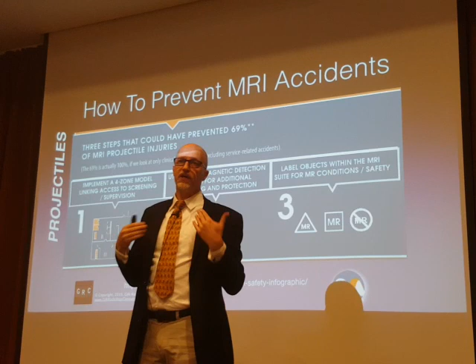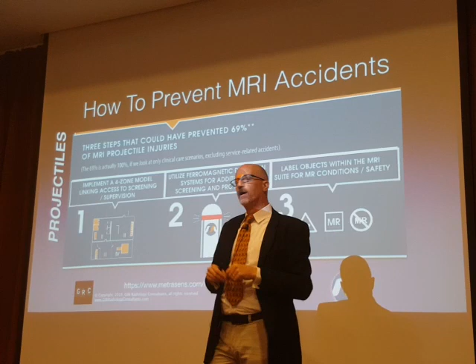For those of you who may not be familiar with the ACR 4-zone, essentially it means the closer we get to the magnet, to the MRI, or to the room that has the MRI in it, the more we're going to make sure that individual is screened or trained, or we are going to lock them out. Unless they're screened, trained, and supervised. So it's a bullseye. As you move closer towards that center ring, towards zone 4, where the MRI is, you have to go through increasing levels of screening, security, and supervision. And that's the basic premise of the ACR 4-zone.